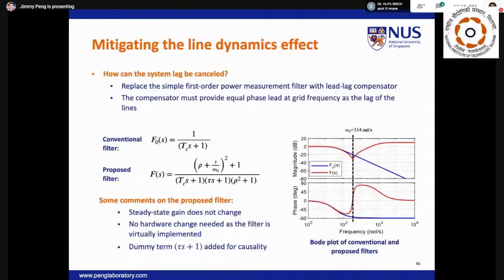We shall modify the existing low-pass measurement filter into a lead-lag compensator. The compensator should provide the exact phase lead to nullify the phase lag of the lines. The proposed filter is expressed as f of s, where tau s plus 1 is a dummy term inserted to ensure the transfer function is causal. It should be set with a sufficiently small time constant, much less than Tc.